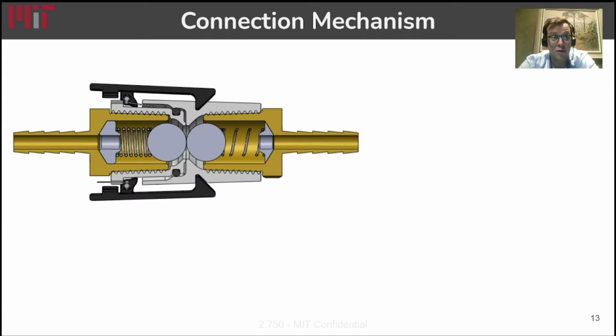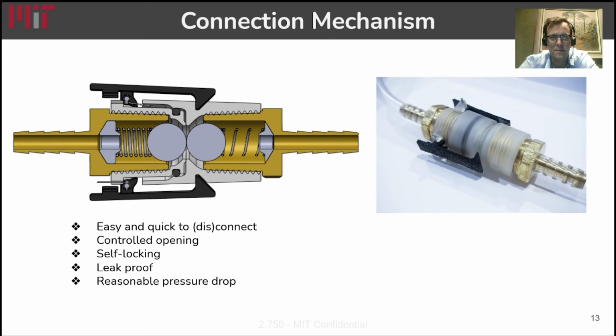For our final prototype, a quick connect connection was designed using a mix of off-the-shelf components and 3D printed parts. On the left, you can see a cross-section of our design, and on the right, a picture of it. The spring and ball system makes this system easy and quick to connect and disconnect. It also enables for us to design the opening sequence of the chambers, controlling the disposal of the sterility fluid as intended, from the disposable to the catheter connection.